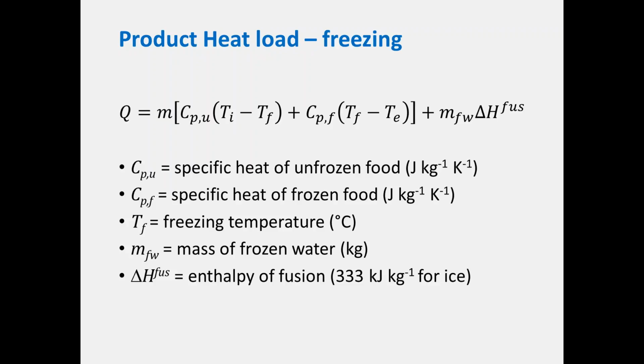Freezing is more complicated because of ice formation. Unlike pure water, which freezes entirely at 0 degrees Celsius, food products have water effectively dissolved within them, so freezing occurs over a range of temperatures. There's an initial freezing temperature, which I call TF, typically between -1 and -3 degrees Celsius for foods. But not all the ice forms at that temperature - ice continues to form as temperature drops further, and even at -40 degrees you won't necessarily get all the water in the food completely frozen.